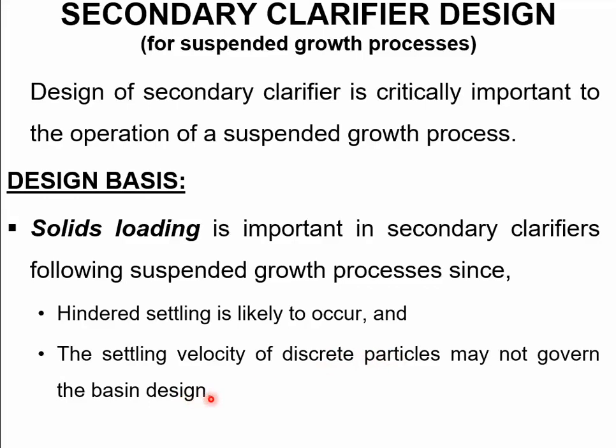If you recall, we designed the primary clarifier on the basis of discrete particle settling velocity. But here in secondary clarifier, since hindered settling is likely to occur, therefore, this should not be used as a design criteria. What is to be used is solids loading rate.